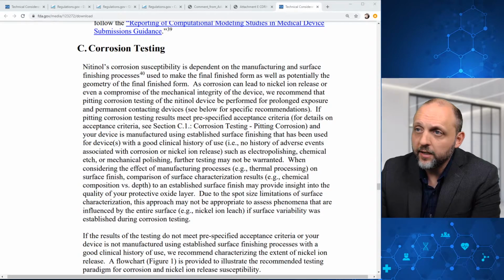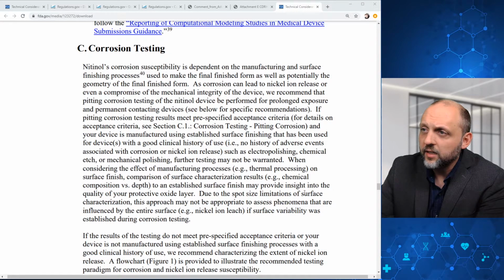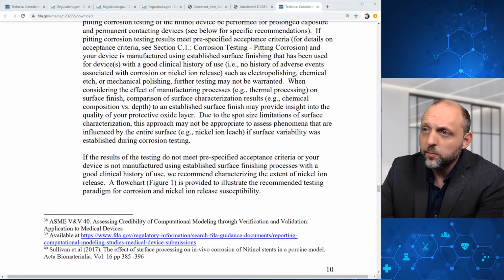When considering the effect of manufacturing processes on surface finish, comparison of surface characterization results to an established surface finish may provide insight into the quality of your protective oxide layer. Due to the spot size limitations of surface characterization, this approach may not be appropriate to assess phenomena that are influenced by the entire surface if surface variability was established during corrosion testing. And if the results of testing do not meet pre-specified acceptance criteria, or your device is not manufactured using established surface finishing processes with a good clinical history of use, FDA recommends characterizing the extent of nickel ion release. And a flowchart is provided to illustrate the recommended testing paradigm.